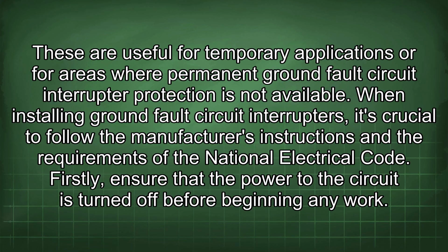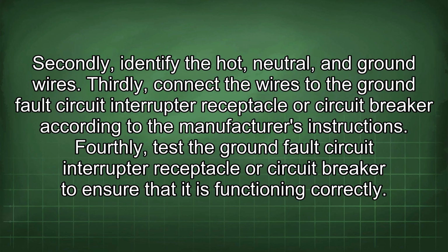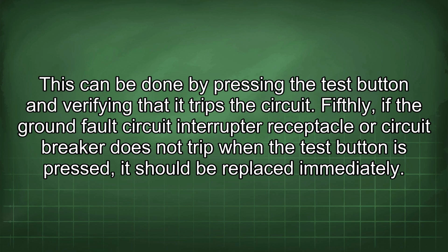When installing ground fault circuit interrupters, it's crucial to follow the manufacturer's instructions and the requirements of the National Electrical Code. Firstly, ensure that the power to the circuit is turned off before beginning any work. Secondly, identify the hot, neutral, and ground wires. Thirdly, connect the wires to the ground fault circuit interrupter receptacle or circuit breaker according to the manufacturer's instructions. Fourthly, test the receptacle or circuit breaker to ensure that it is functioning correctly. This can be done by pressing the test button and verifying that it trips the circuit. Fifthly, if it does not trip when the test button is pressed, it should be replaced immediately.